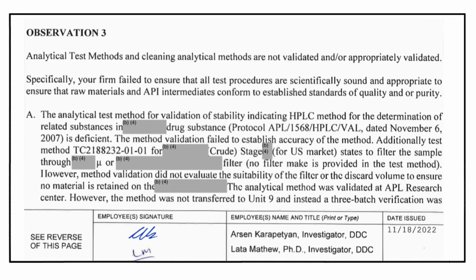Observation number 3: analytical test method validations and cleaning analytical method validations were not done appropriately. Auditors verified the analytical method validation of the RS test and found that the filter validation study was not done during the analytical method validation. This study is usually performed to demonstrate whether filtration has any effect on the analysis results, and based on it, the type of filter to use and the amount of sample to discard during filtration are decided. Auditors found that this filter validation study was not performed during the analytical method validation.